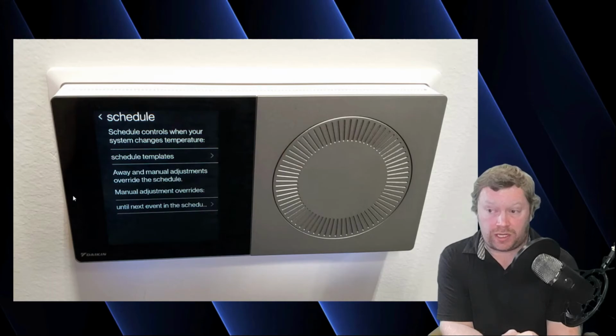The bottom selection, manual adjustment overrides, is what you'll program to allow for an override. Typically the way it works out of the box is you'll have a 6 a.m. action in the schedule that says turn on heat at 70 degrees. But that's a one-time action. So the schedule acts like an invisible person standing there who does something at 6 a.m., and your Daikin 1 will stay there until it's told to change. It'll either be told to change because you walk up and change it, or you log into your app and change it, or another action later in the day changes it on the schedule. We call that last command wins.